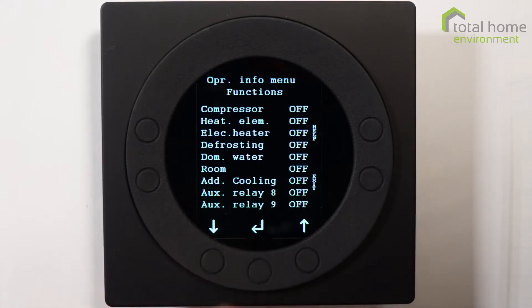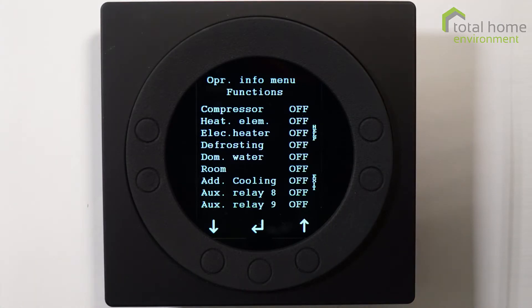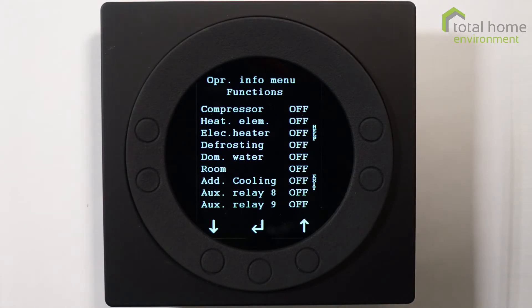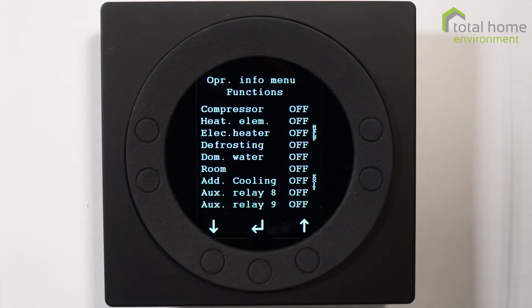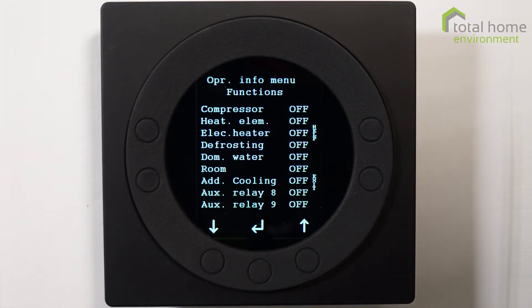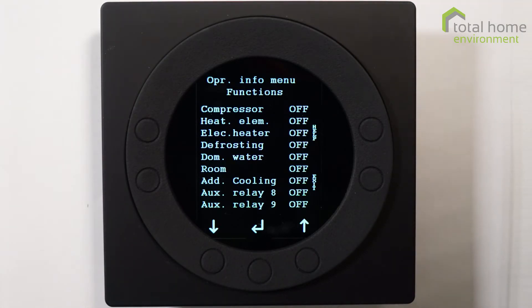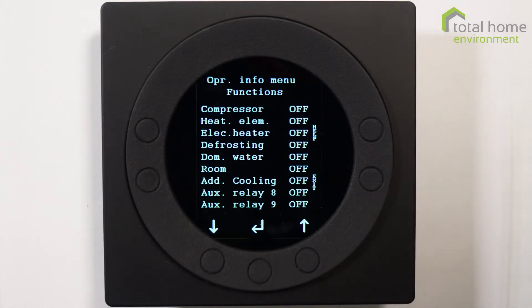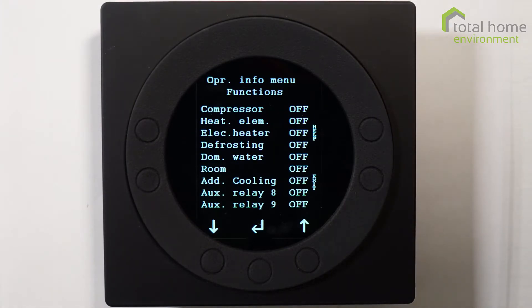If I press the down arrow that gives us another page and this tells us what functions are operational. Compressor is actually your heat pump. Heating element is the immersion heater. Electric heater, if there is one fitted, is a duct heater. Defrosting is an automatic mode which occurs when the pre-cooling surface and the evaporator coil reach certain temperatures, at which point the machine automatically provides hot gas to the evaporator coil to melt any ice that has formed.